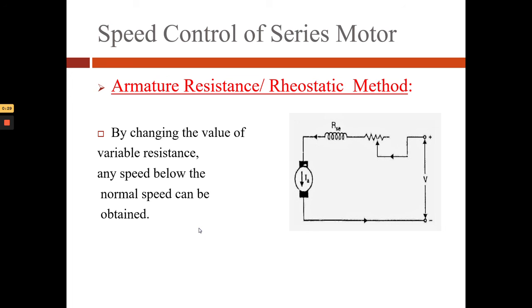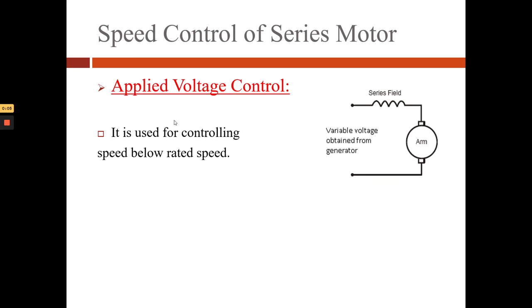Now we will see armature rheostatic control. Due to insertion of the rheostat R in series with the motor, the armature current flows through it and there is a voltage drop of IR across it. The voltage across the armature winding reduces and the speed also reduces, because speed is proportional to armature voltage. By changing the value of the variable resistance we can control the speed. This method is used for controlling speed below rated speed.